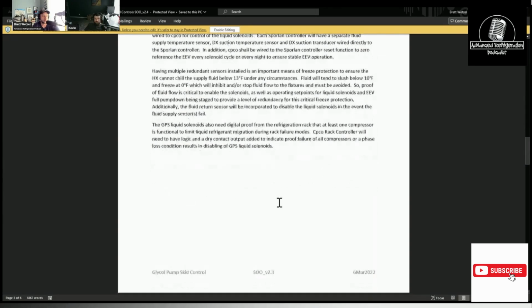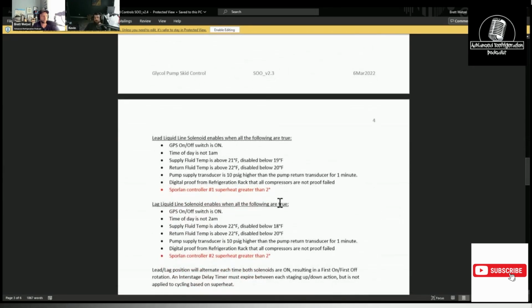Correct. I'm still trying to figure out how to get on those with the laptop. I started to look at it, and yeah. So here, supply fluid temperature above 21. Disable at 19. Return flow temperature above 22. Disable at 20. Pump supply transducer 10 pounds higher than the return for 1 minute. So lead liquid line enables for these follow reasons.